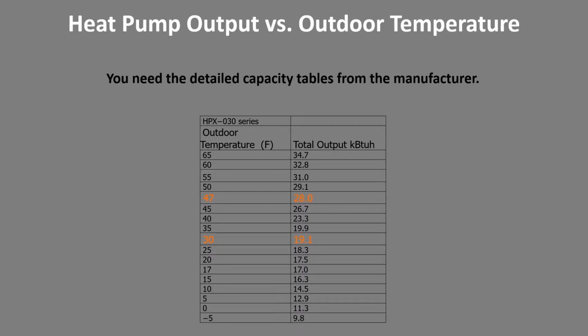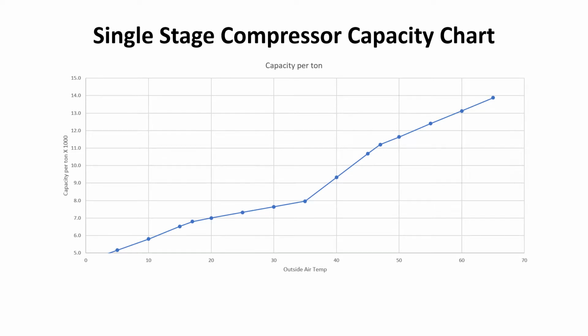This is a detailed capacity from a manufacturer. Some of you might recognize the brand. This is interesting. It's a 2.5-ton unit, and at 47 degrees, their 2.5-ton unit gives you 28,000 BTUs. Not exactly a 2.5-ton machine, but close to it. It's like a 2x4. It's a nominal value, and we should always look at the detailed capacity table. So this is the capacity of a single stage system, if you will. Down here on the bottom axis, we have the outdoor temperature ranging from 0 all the way up to 70.